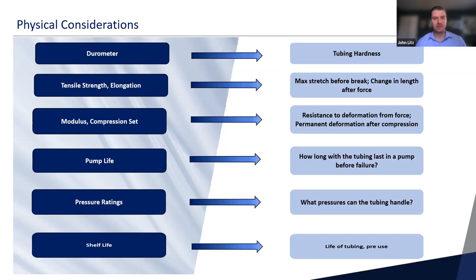So touching on deformation of tubing, next we're going to be moving to modulus and compression set. And modulus is the resistance of deformation from force. Modulus can be very important for pump tubing applications because you're going to want to make sure that it has a good resistance to deformation. One thing that you'll commonly see in pump applications is tubing compression. And essentially, when you think of tubing, you think of a circular inner diameter of the tubing that helps maintain consistent flow rates. And in certain cases, if you have a tubing with an inappropriate modulus or compression set, you might see ovality occur on the tube, which can affect flow rates and it can affect the success of the tubing in a pump application.